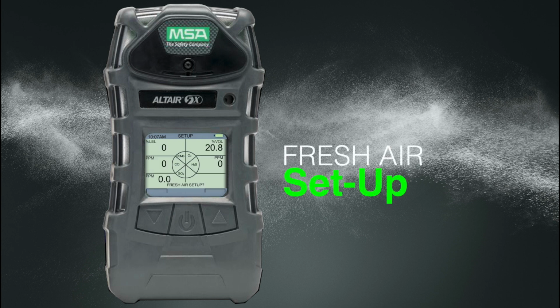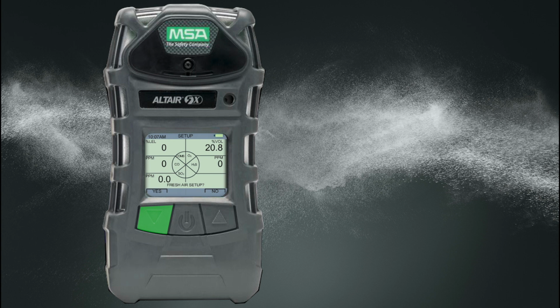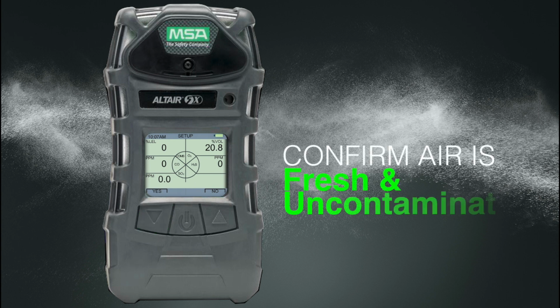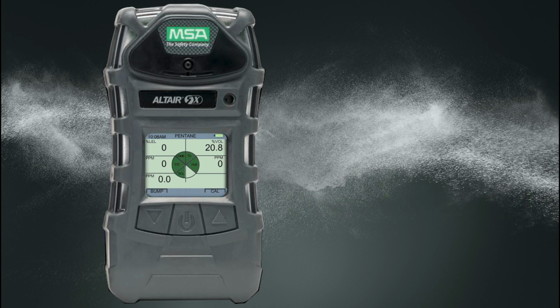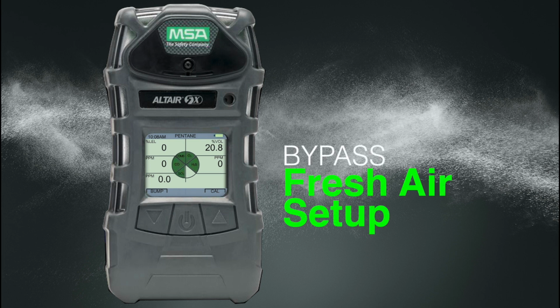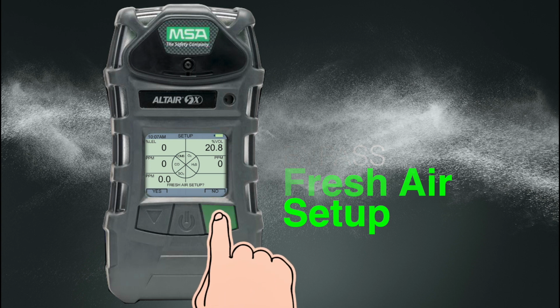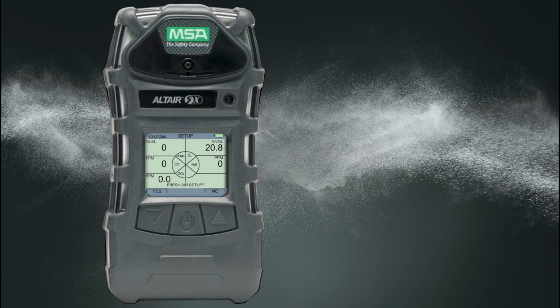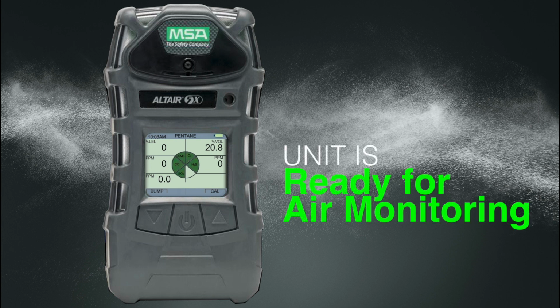When the fresh air setup display is flashing, perform the setup. You will have 10 seconds to activate the setup. To perform the fresh air setup, press the down arrow button briefly. Do not activate the fresh air setup unless you are confident you are in fresh, uncontaminated air. Otherwise, inaccurate readings can occur, which can falsely indicate that a hazardous atmosphere is safe. If you have any doubts as to the quality of the surrounding air, do not use the fresh air setup feature. To bypass the fresh air setup, press the up arrow or wait 10 seconds. Failure to follow this warning can result in serious personal injury or death. The unit is now ready for air monitoring.